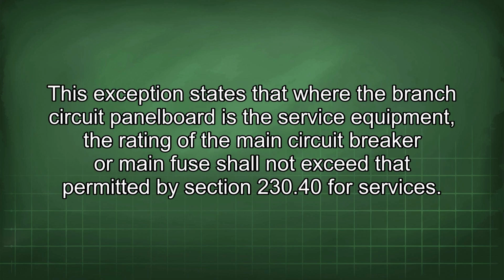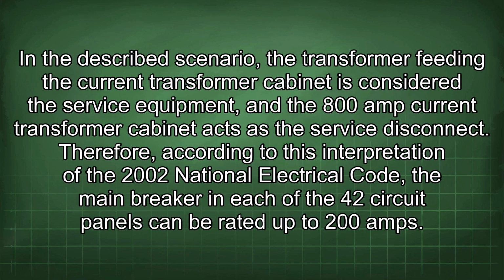This exception states that where the branch circuit panel board is the service equipment, the rating of the main circuit breaker or main fuse shall not exceed that permitted by Section 230.40 for services. In the described scenario, the transformer feeding the current transformer cabinet is considered the service equipment, and the 800 amp current transformer cabinet acts as the service disconnect. Therefore, according to this interpretation of the 2002 National Electrical Code, the main breaker in each of the 42 circuit panels can be rated up to 200 amps.